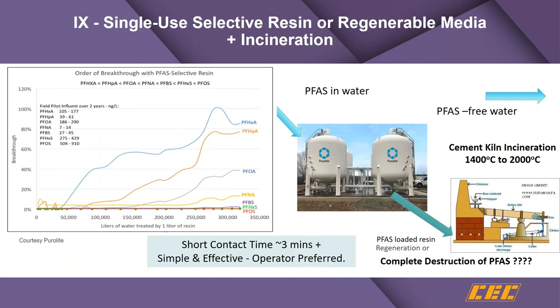Ion exchange is another technology. These typically have a shorter contact time, meaning smaller vessels. The media itself is more expensive than granular activated carbon. Carboxylates — those ending in A — are much more difficult to remove than sulfonates, which typically end in S. Ion exchange may achieve several hundred thousand bed volumes before it has to be regenerated.